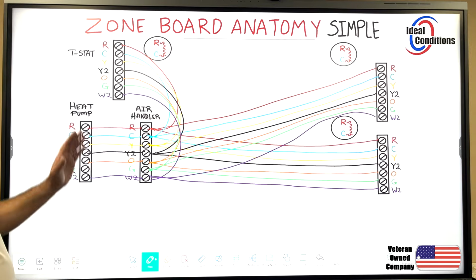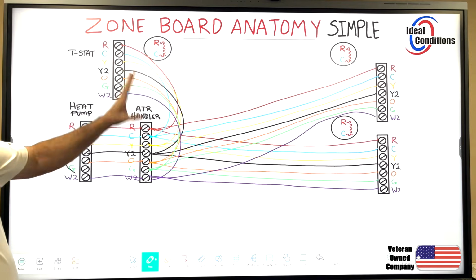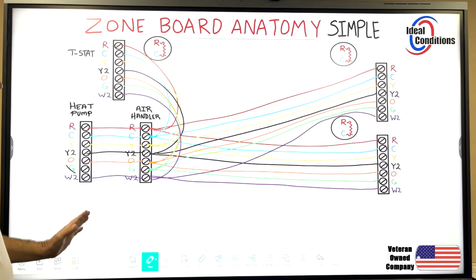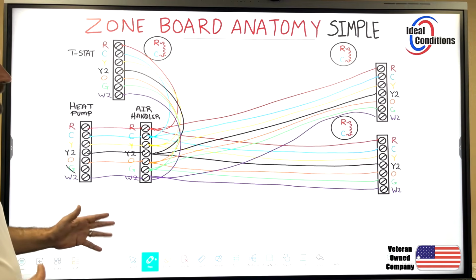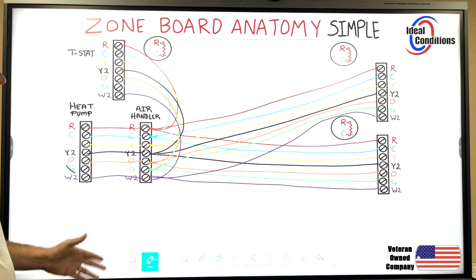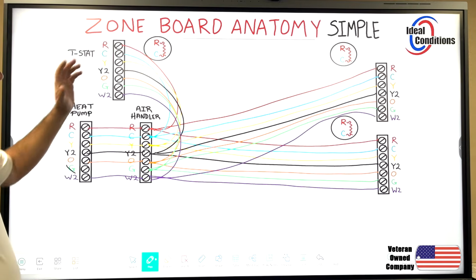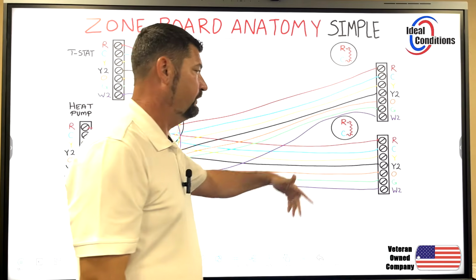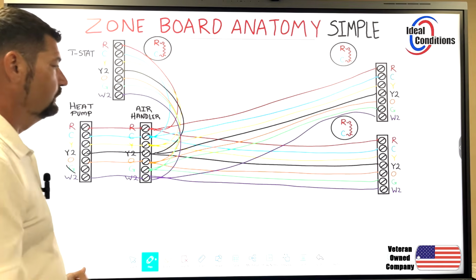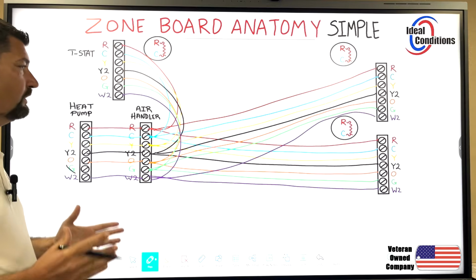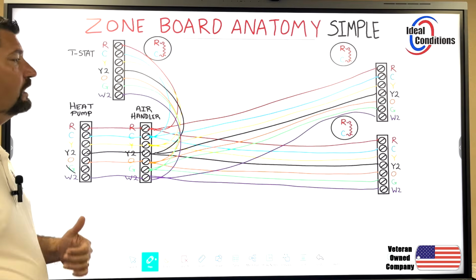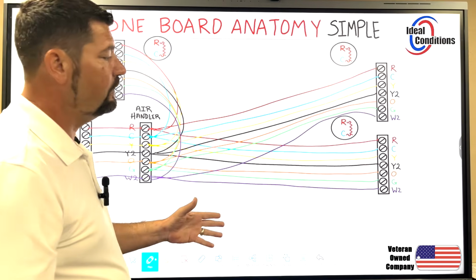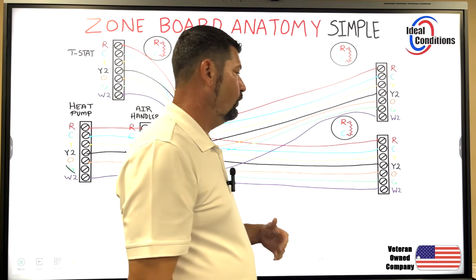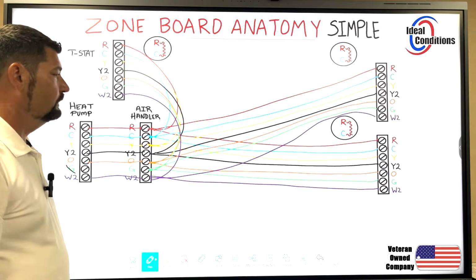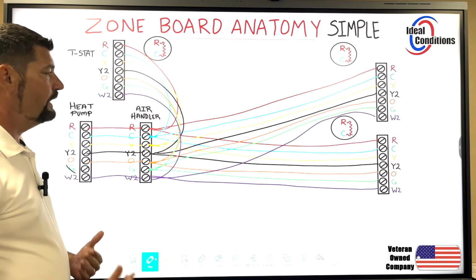We've just taken the air handler, the condenser, and 3 thermostats, and said, hey, there's really no zone system here. We just have thermostats all over the place, and they're all in parallel with each other. When things are all in parallel, one thermostat is pretty much the same as having 3 thermostats. You're just going to get a balance of temperature, but what you cannot control is one area of the house overcooling or overheating. So that's not a way to zone.